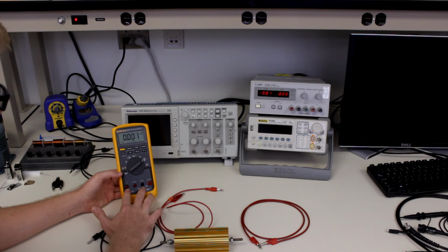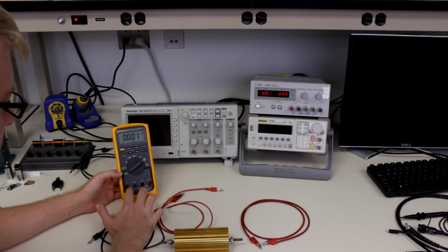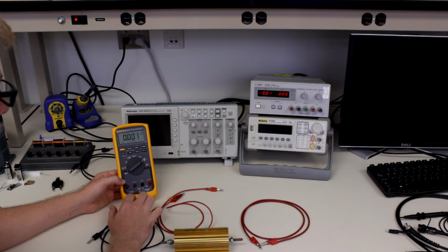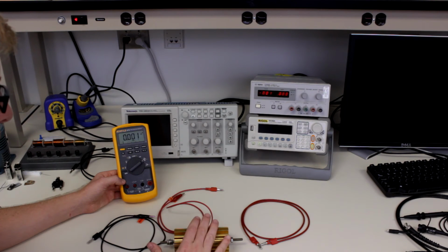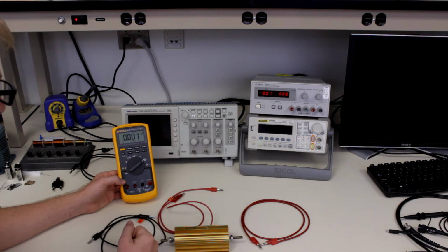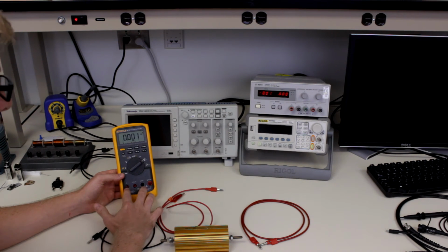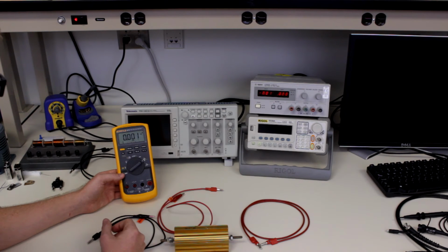Now we need to be very careful in making connections to these terminals because of the fuses that are involved. So we always want to limit the current flowing through the system using a resistor or some other device. We never want to connect these directly to a power supply because it will blow the fuses in here, and these fuses are actually quite expensive.